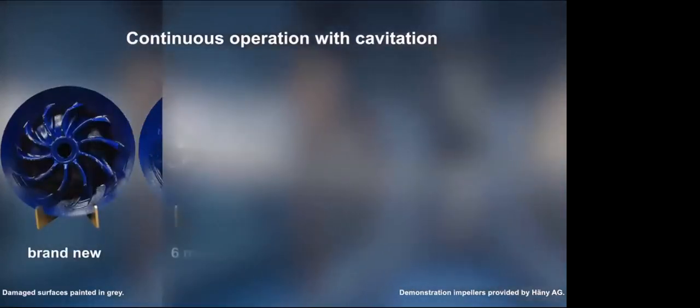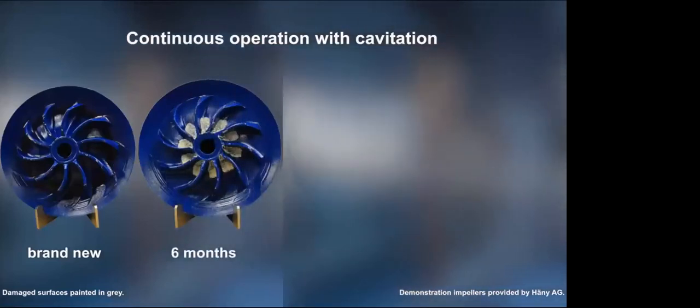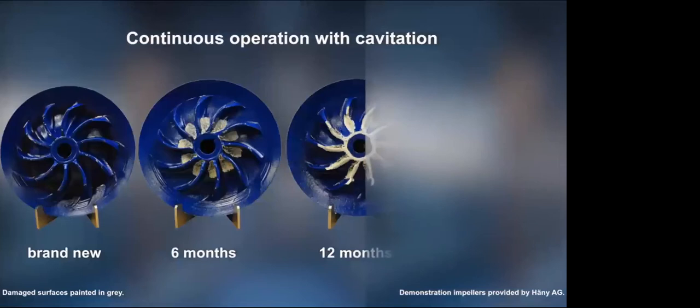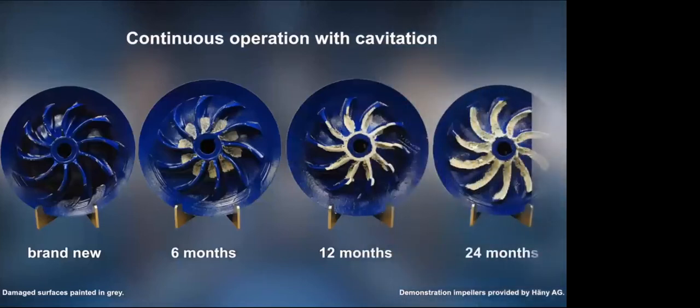We show a few examples of damage in pump impellers kindly provided by the Swiss pump manufacturer Häny. A brand new impeller to the left, in comparison with an impeller having been continuously exposed to cavitation during 6 months, another impeller with damage from 12 months operation in cavitation, and one from 24 months.